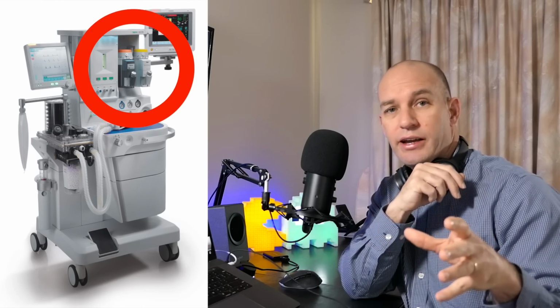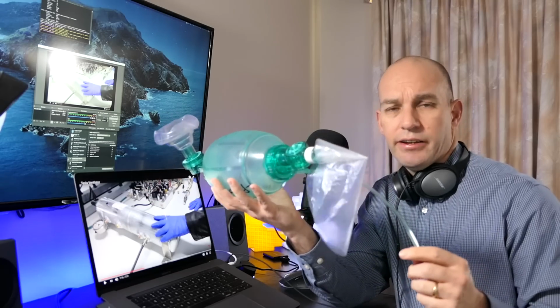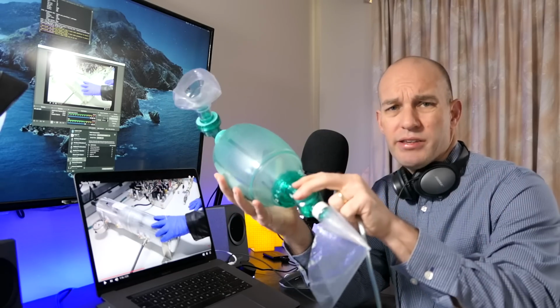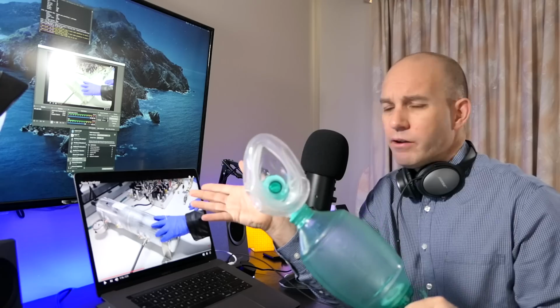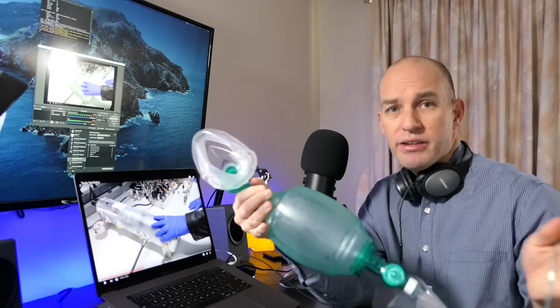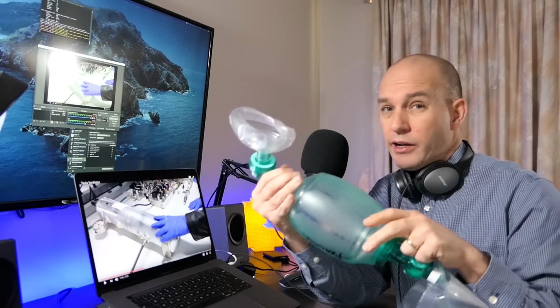Okay, so this is fascinating and a very good sort of primer. This chamber here, inside ventilators and anesthetic machines, they have a mixing chamber, and they take in medical air and they take in oxygen, and they can take in nitrogen. And with anesthetic machines, they also have a volatile anesthetic agent that can be like sevoflurane or something like that, and it gets mixed in a chamber. And unlike the Air-viva, just give me a second, that you can only actually set in oxygen or maybe room air by taking off this end piece. Ventilators and anesthetic machines, they actually mix this all together before it gets sent out to the patient. So key important difference there.